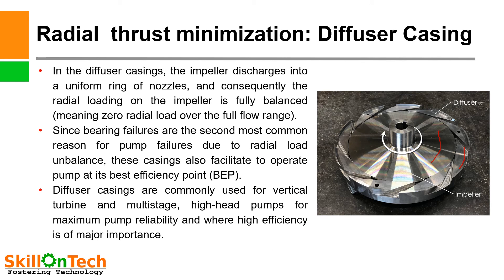Radial thrust minimization: Diffuser casing. You can see a picture of a diffuser casing here — this is the impeller, and this is the diffuser casing where guide vanes have been provided at every stage at the discharge of the impeller. In the diffuser casing, the impeller discharges into a uniform ring of nozzles, and consequently the radial loading on the impeller is fully balanced, meaning zero radial load over the full flow range.